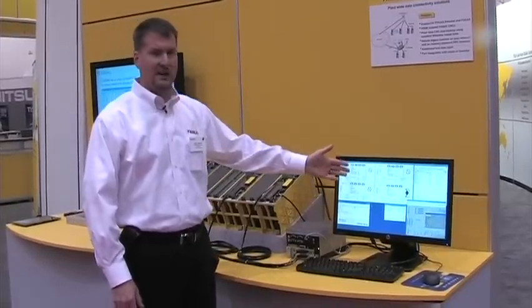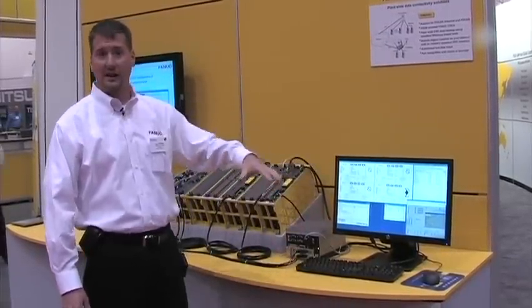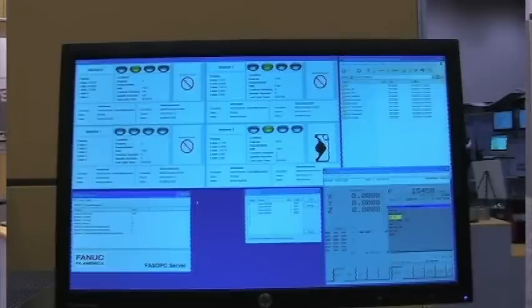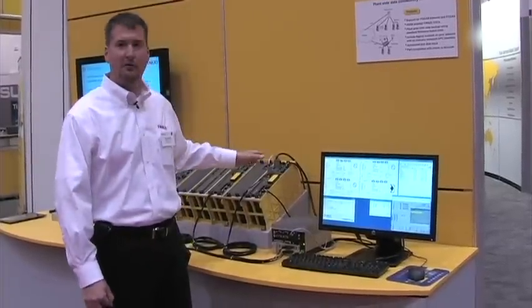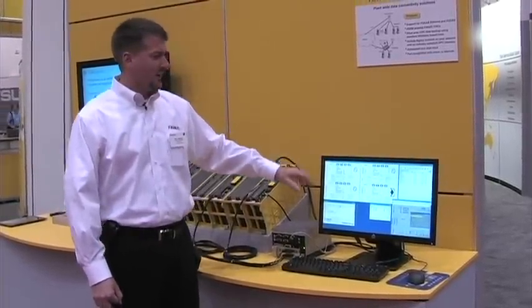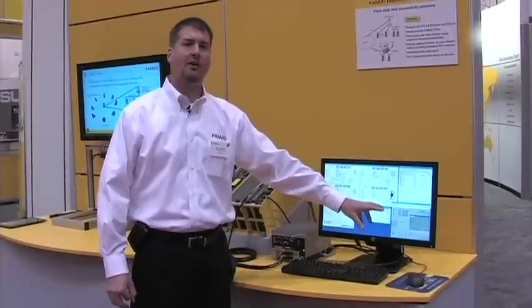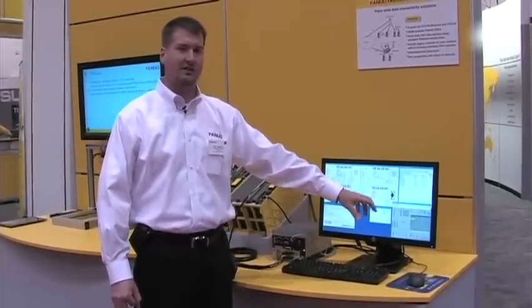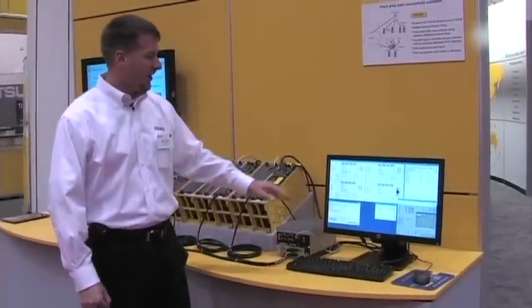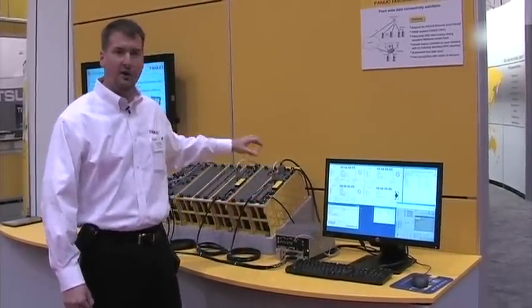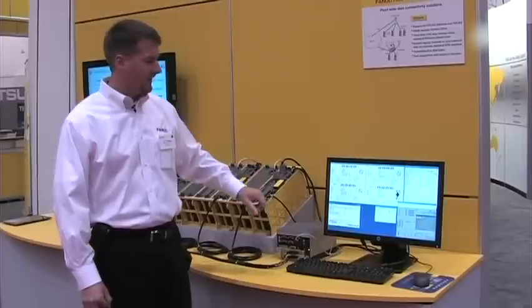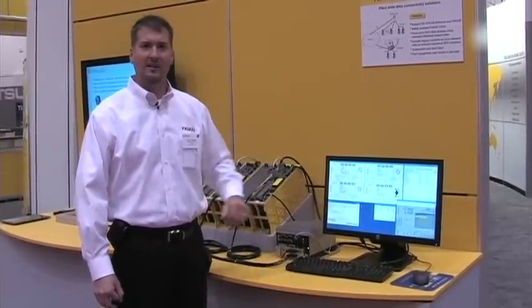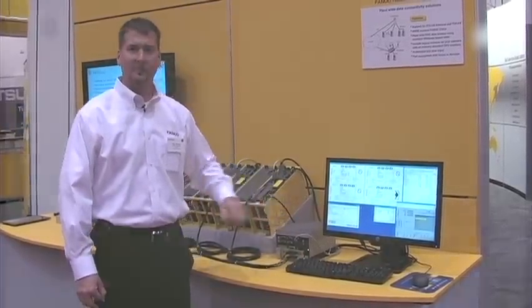This display is actually a PC that's running in the network, not connected to this. We're also showing the OPC client, a simple client written, showing the data coming from these machines. The CNC screen display is also running, allowing to drill down into the CNC and view the display on the CNC. But all data is being converted from older HSSB protocol to new OPC protocol within this box itself.